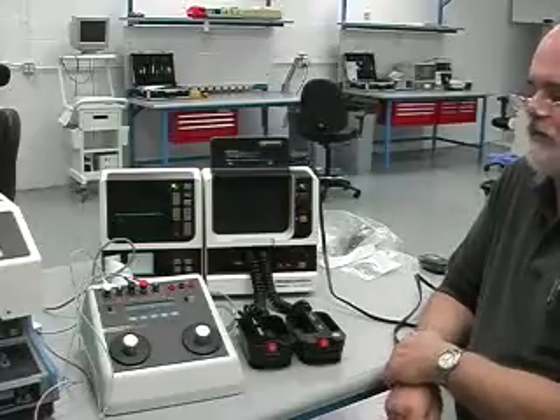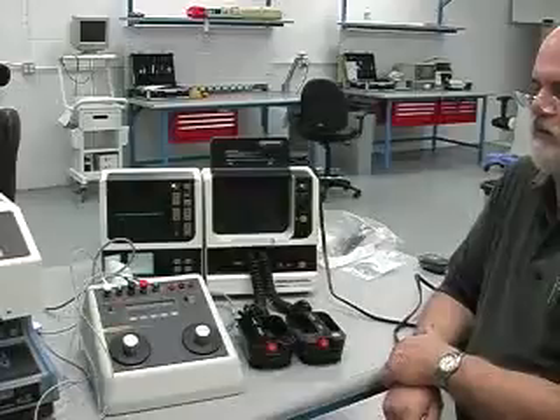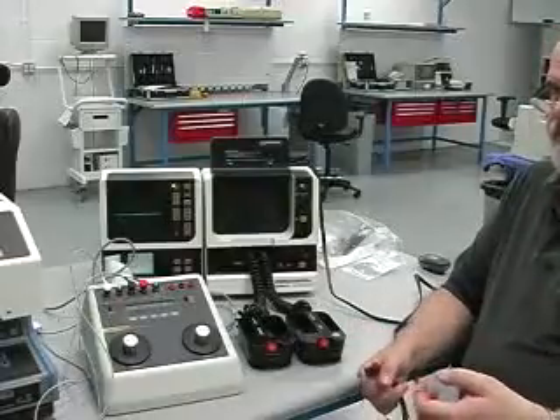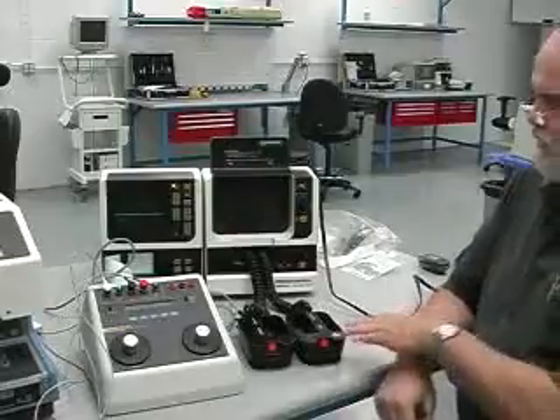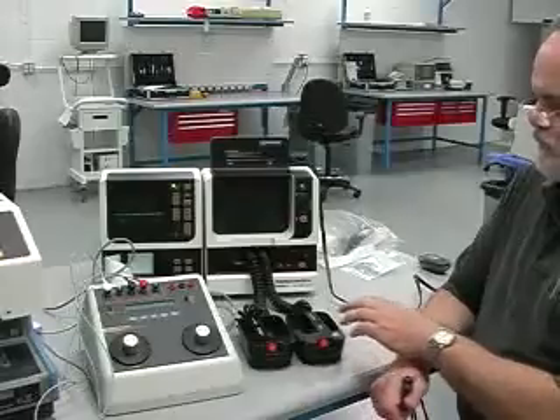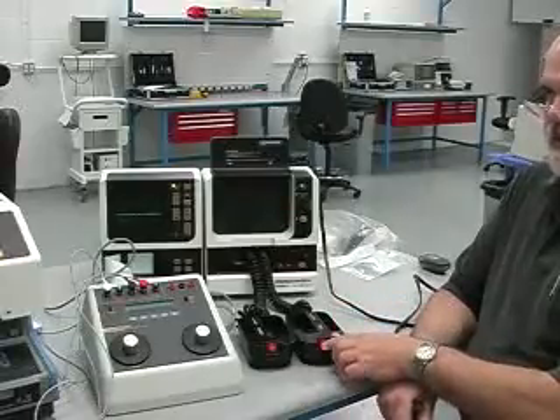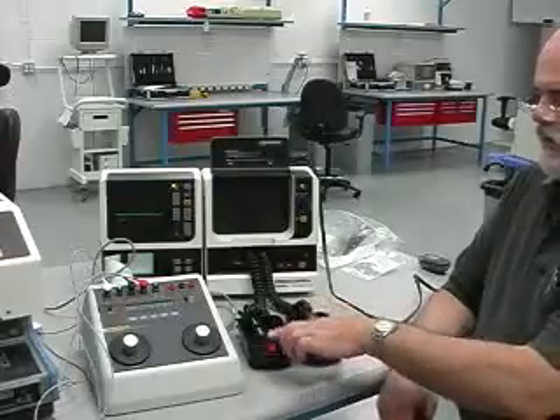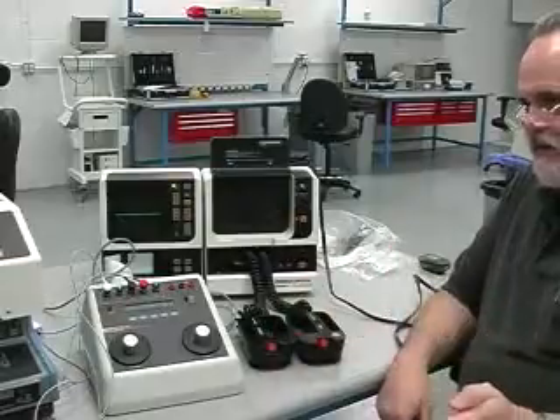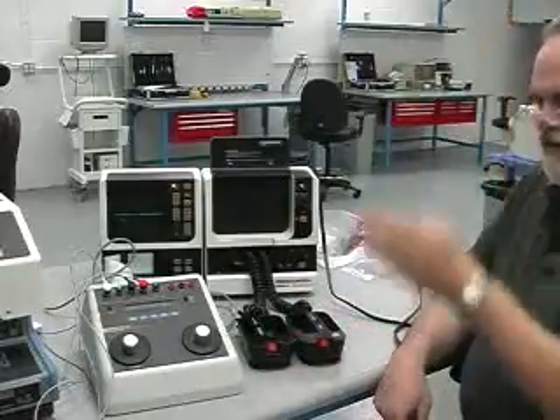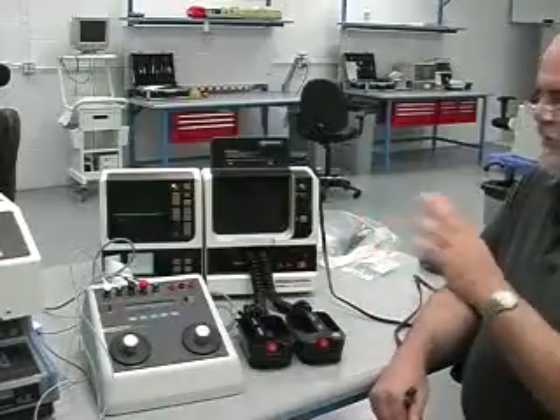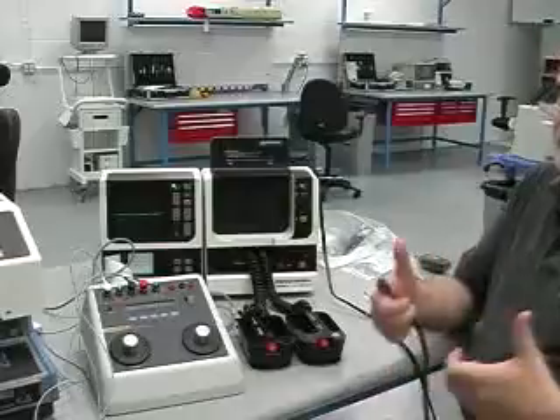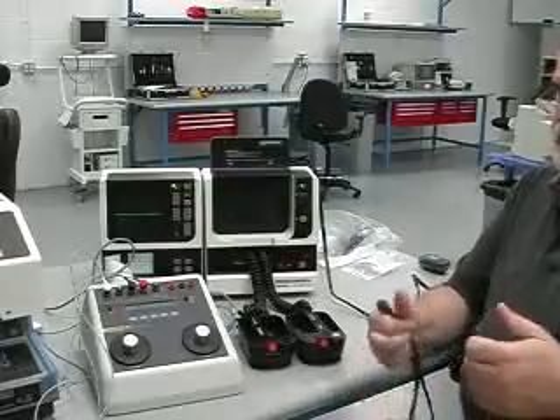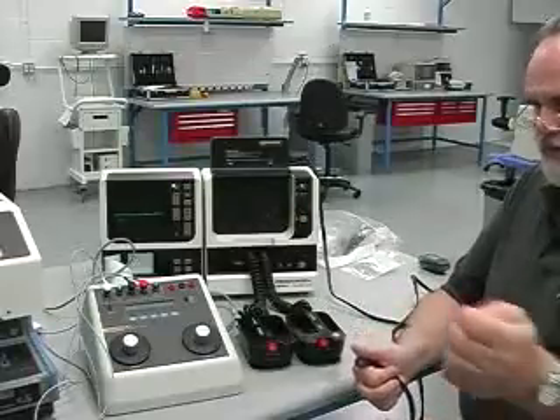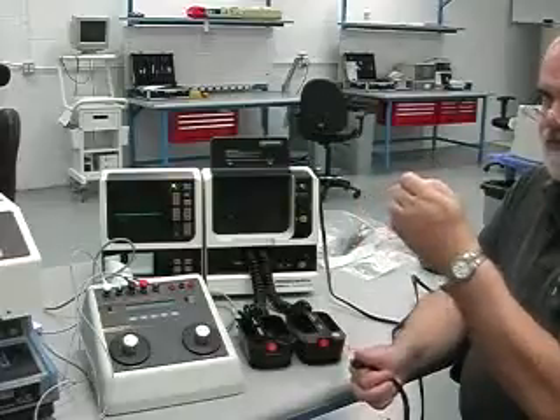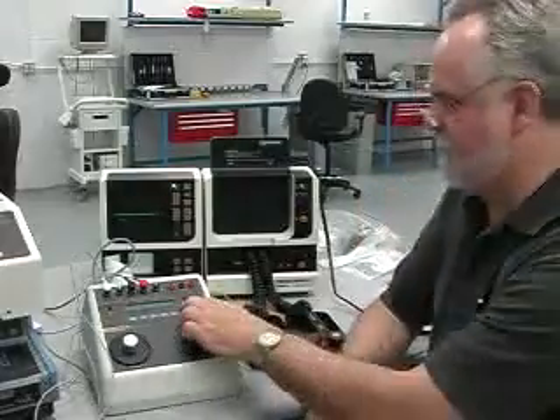Okay. There's really no need for you to be concerned with that, because what will happen is the defibrillator isn't discharging when you push these discharge buttons down. It will only discharge when you have those buttons pushed down, and then after that the ECG comes through, then it will discharge. So in this one condition, the defib isn't discharging immediately when you push the buttons. It's charging only if you've got the buttons pushed, and only when the ECG waveform comes through, then it will do it. I can demonstrate that a little bit differently. It'd be easier for you to see it.